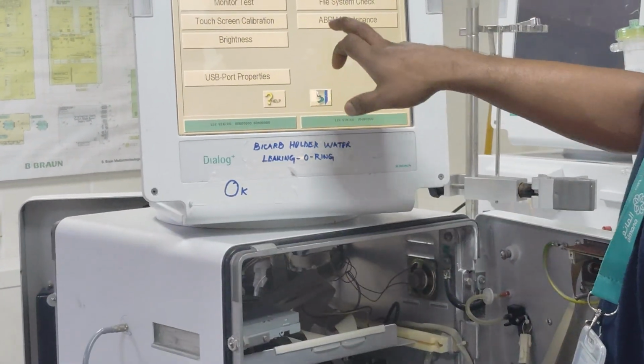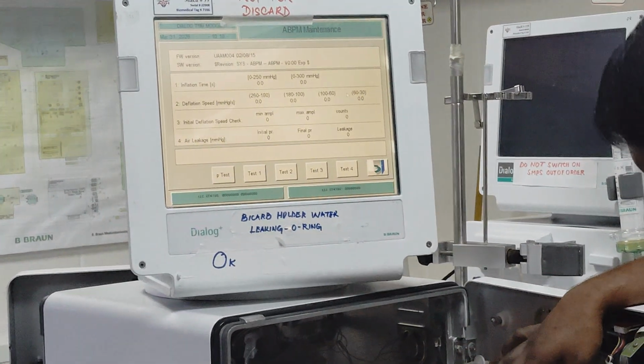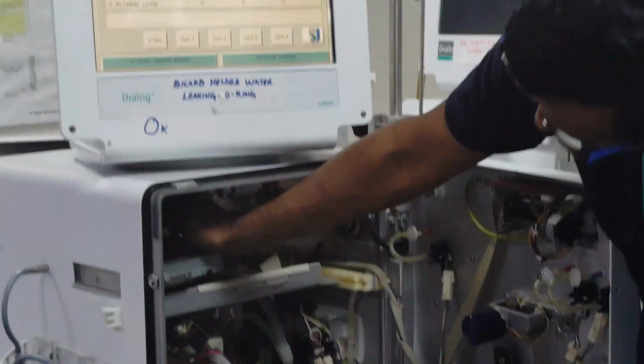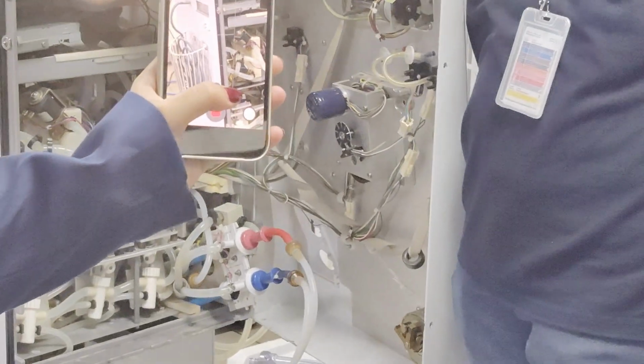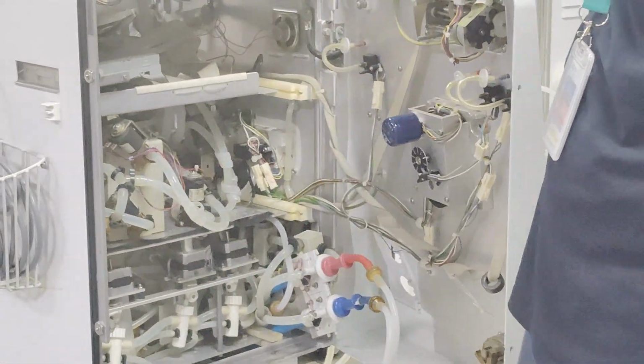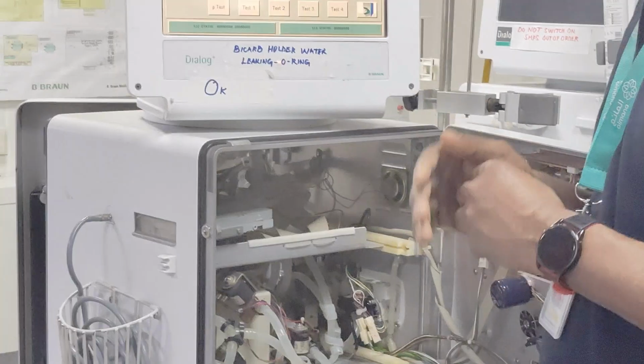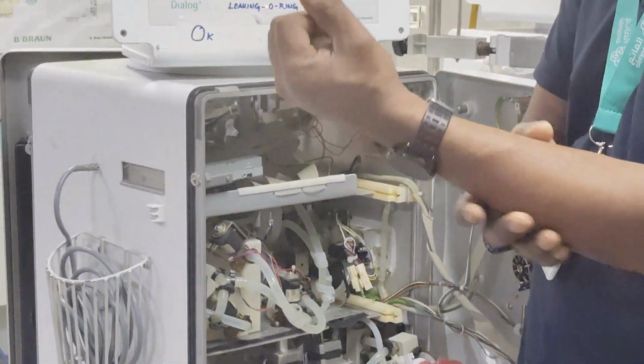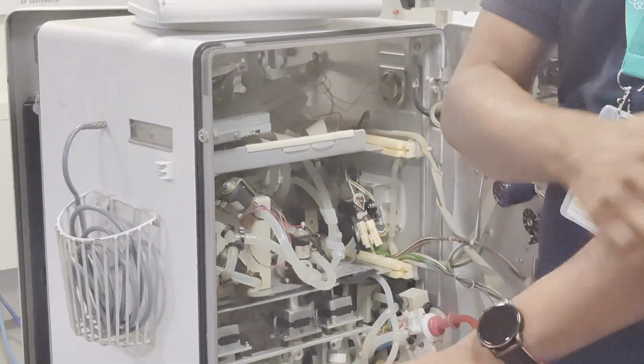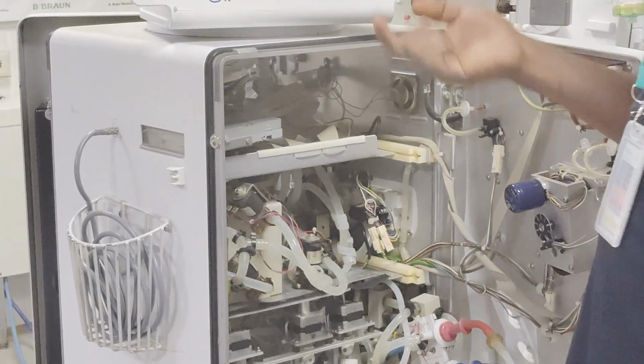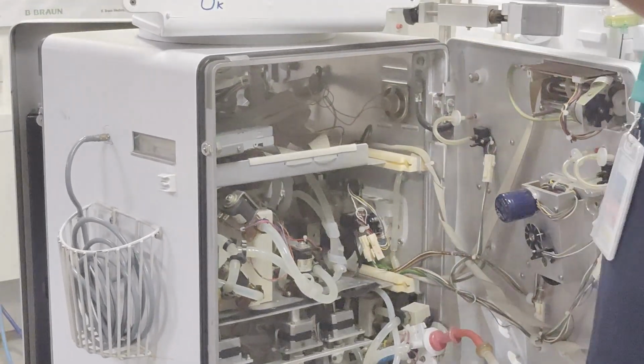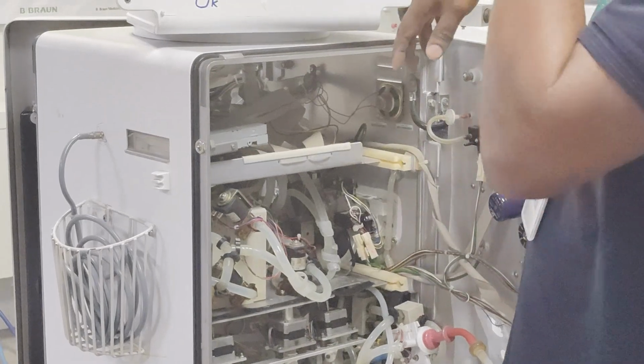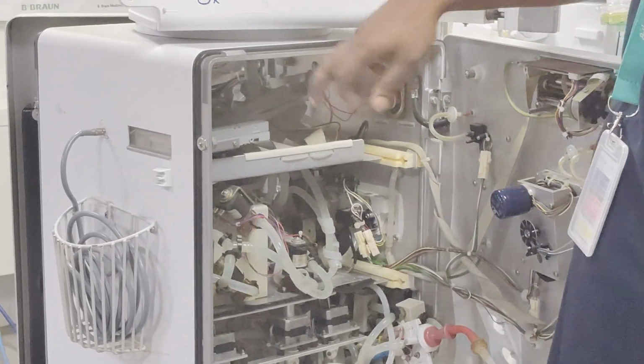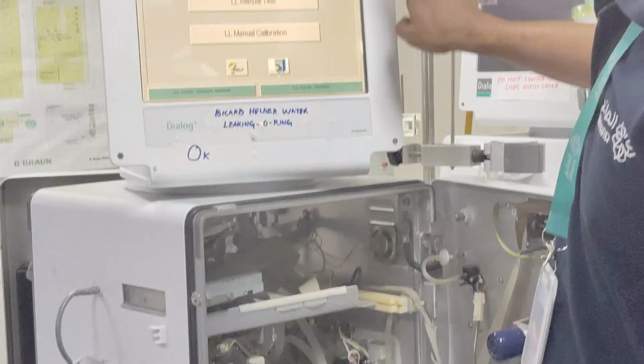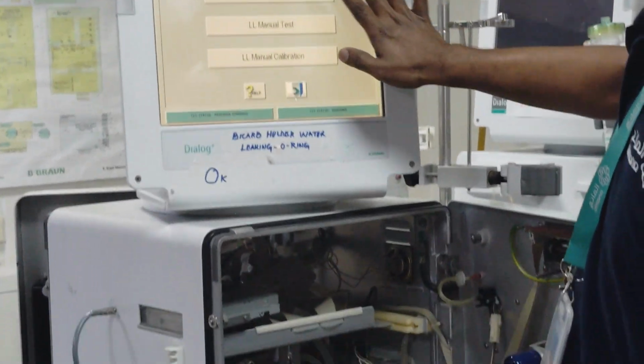And the ABPM maintenance. ABPM maintenance is like, we have an ABPM module here. You can see the ABPM module inside. It is a blood pressure module and it is connected down below. So we can do different tests. If the staff is complaining that it is not inflating properly, or there are inflation issues, in that case we can do the testing one by one. We have some test tools to check whether the inflation is okay or not, or whether there are leaks or anything. So these are the only things we have seen today for testing.